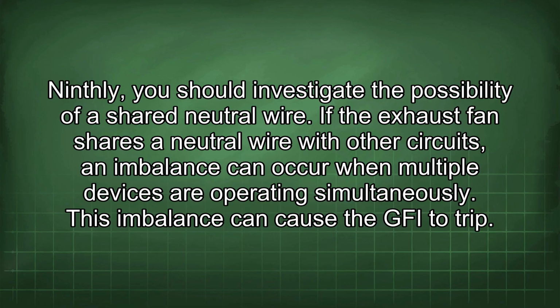Ninthly, you should investigate the possibility of a shared neutral wire. If the exhaust fan shares a neutral wire with other circuits, an imbalance can occur when multiple devices are operating simultaneously. This imbalance can cause the GFI to trip.